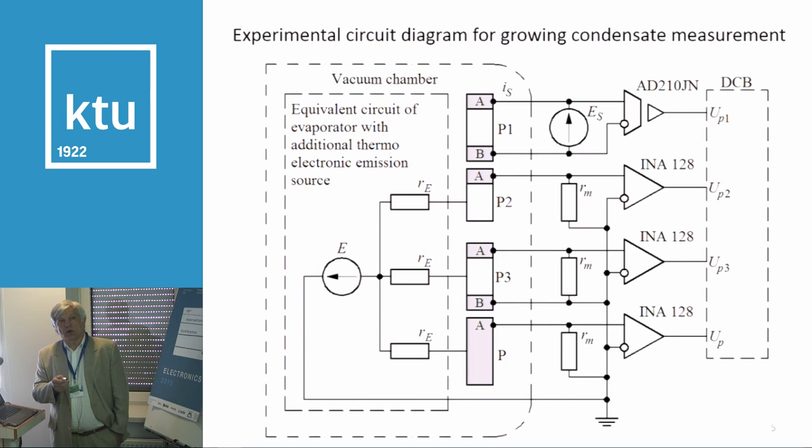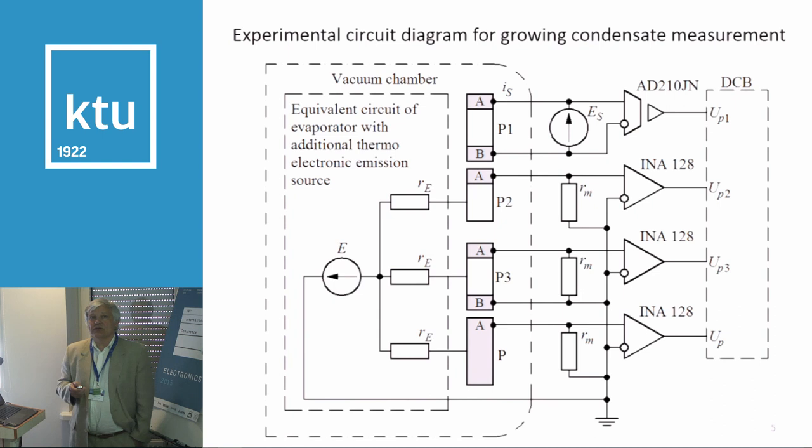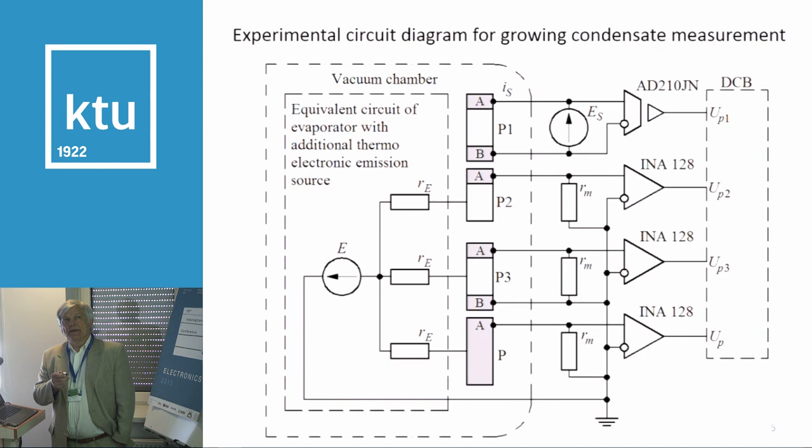And the one contact probe. This contact is grounded through this resistance, and for control we used the traditional method of resistance measurement with two contacts and stabilized current, with a low voltage, if I remember, 7 volts. The current is very small, and we use an optically isolated amplifier. And this probe has no electrical connection with the other electrical circuits.